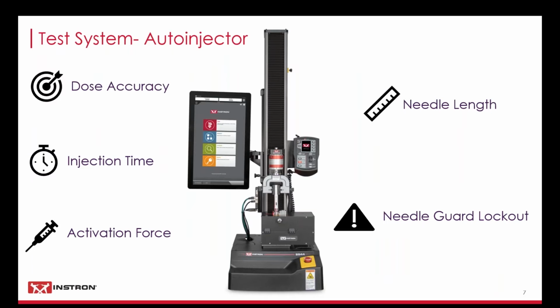In the past, many of these functions had been tested individually, forcing manufacturers to use multiple pieces of equipment and manually sort through all of their data to synchronize the results. This process slows down design evaluation and testing, potentially affecting time to market. With the growth in the injectable device market came a growing need for fully integrated testing systems. Consolidating these tests can be done with a standard electromechanical frame and the addition of specialized equipment such as optical micrometers and precision scales.